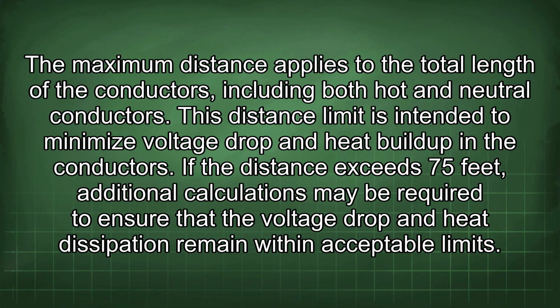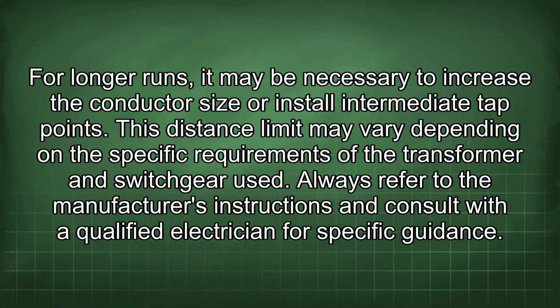If the distance exceeds 75 feet, additional calculations may be required to ensure that the voltage drop and heat dissipation remain within acceptable limits. For longer runs, it may be necessary to increase the conductor size or install intermediate tap points. This distance limit may vary depending on the specific requirements of the transformer and switchgear used. Always refer to the manufacturer's instructions and consult with a qualified electrician for specific guidance.